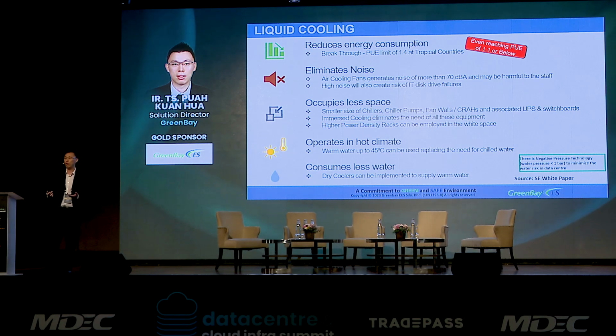With liquid cooling, as you know, there is a water risk in the data center, but some technology offers negative pressure, meaning the whole piping uses water pressure less than 1 bar, since atmospheric pressure is 1 bar. If the water pressure inside the pipe is less than 1 bar, any breakage won't cause leaking of the water or liquid.